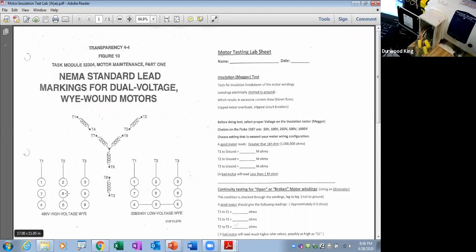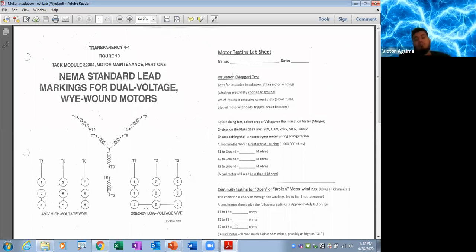So if you're on high voltage on Y, it's actually a series connection on the inside of the motor of everything. If you go low voltage like we did at the school on most of what we did, here's what you got. You're putting your first leg off of the starter on 1 and 7. Your second leg goes to 2 and 8. Your third leg goes to 3 and 9. And then what happens, you got 4, 5, and 6 to go together. You see that? The 4, 5, and 6 go together.